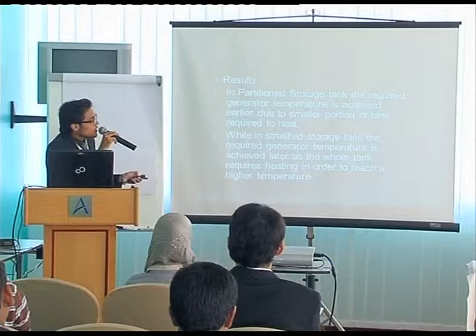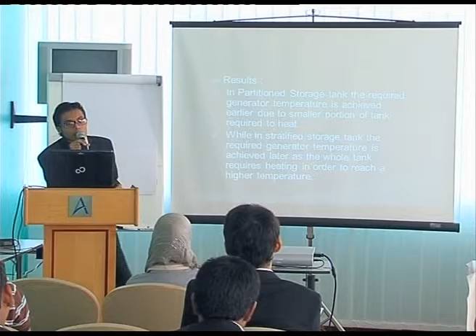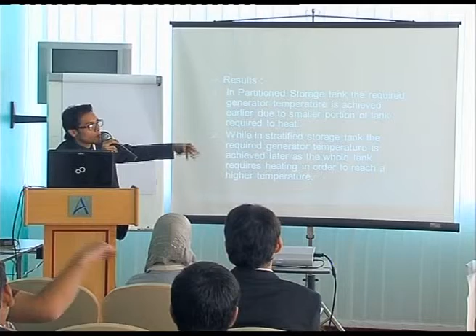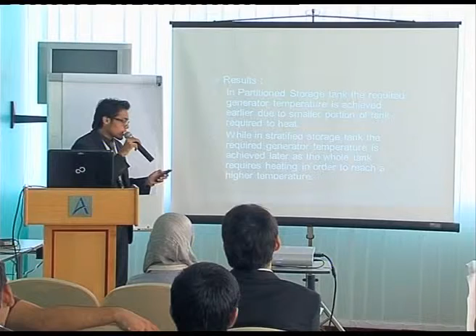And after that, we go to the results. The results were, first of all, in the partitioned storage tank, the generator temperature is normally 88 degrees centigrade, so that the chiller may become operational. Since we have divided our storage tank into segments, only this portion requires heating in the morning.